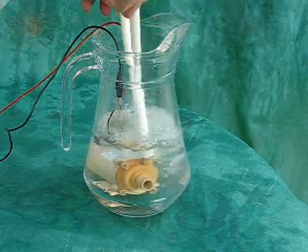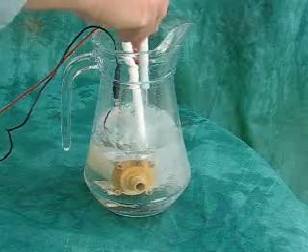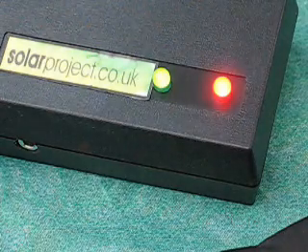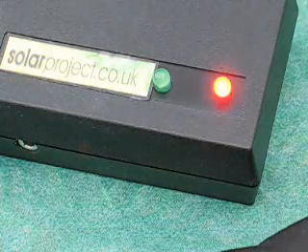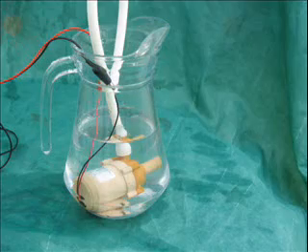At the end of those 20 seconds, the pump is stopped and the temperature is taken again to establish whether there is a need to run a second cycle to eradicate the risk. Once the panel rises above 4 degrees, the pump is switched off and the circuit settles down. It checks itself every 15 seconds.